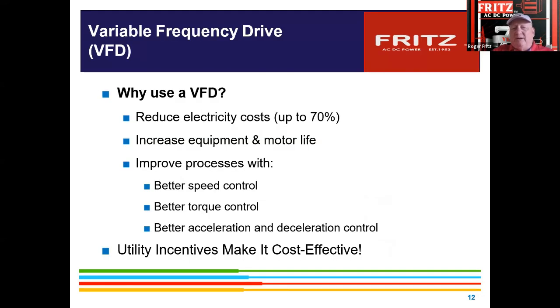Why use it? Reduce electricity costs, up to 70%, especially on very lightly loaded motors or fans and pumps, because of the cube law. It increases motor and equipment life, because you're unloading some of the facilities. We've done plastic processing. We've taken a 2,500 amp service, and after we put drive controls on a majority of the motors on that system, it ended up being around 1,000 amps of current throughout. So it does have some big impact.